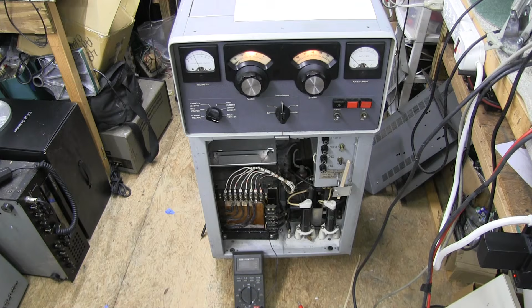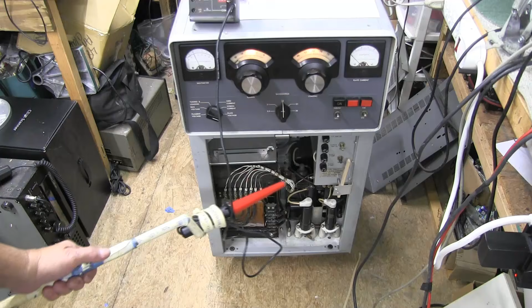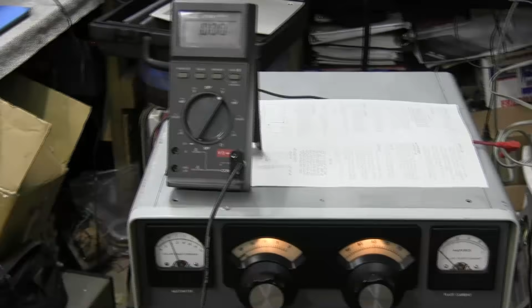I want to check the voltage. If this transformer is putting out 3,000 plus volts, I don't have a meter to check it with, so I'm going to use a high voltage probe. I've got one here on a chicken stick, because a lot of times I don't trust this stuff. Let's zoom in on the meter a little bit.